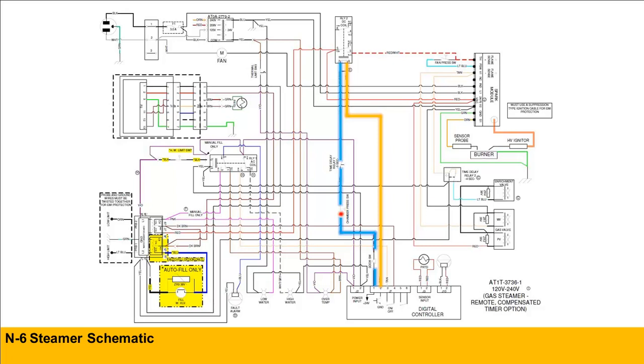So if we test across and show the switch is closed, or we jump it, and we still have no call for heat, then we'll have to actually look at the delay timer. Once again, it's got 2 wires going to it. The common will get power after 5 seconds. That will close, and once again provide power to your DC relay.